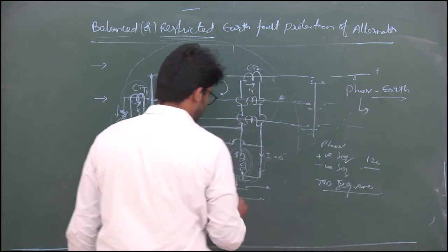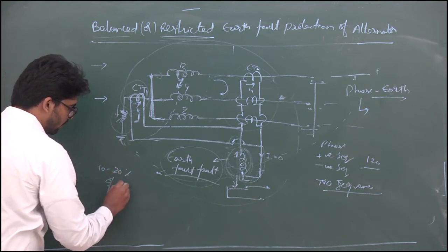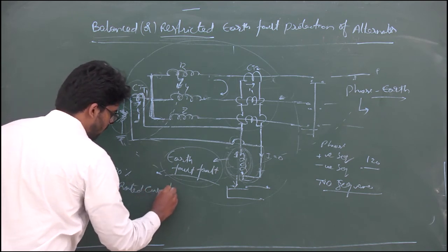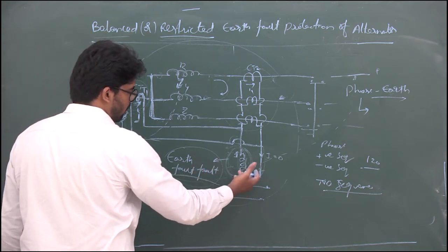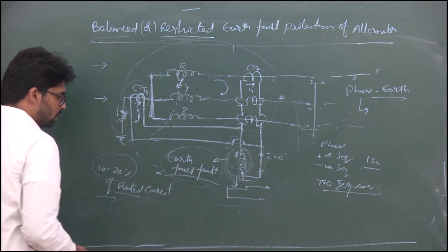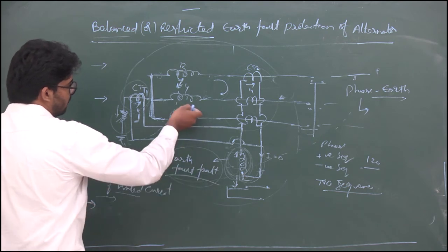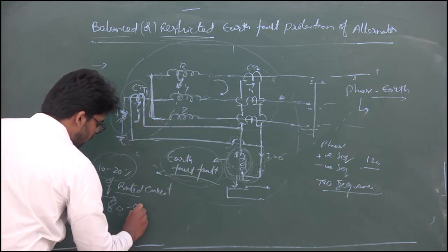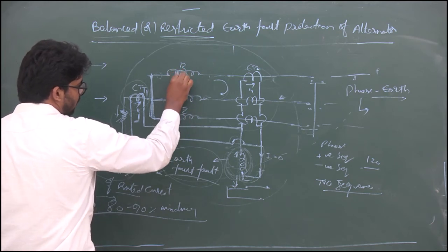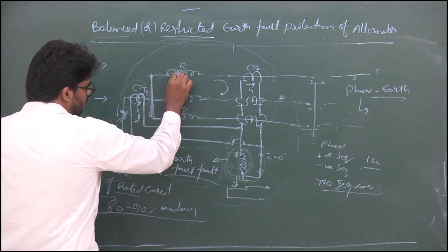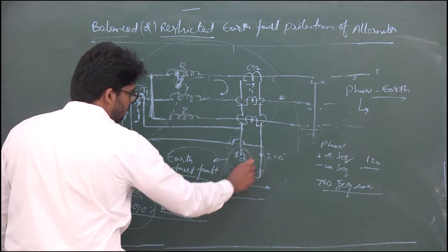In general, this relay coil is configured to operate at 10 to 20 percent of the rated current. So this relay will be operated only at 10 to 20 percent — this design of the relay coil will be rated up to 10 to 20 percent, so it is not needed to operate at higher rated current. This coil will protect about 80 to 90 percent of the winding. If the fault occurs in this winding section, the winding section — about 80 to 90 percent of the winding section — will be protected by this relay coil.